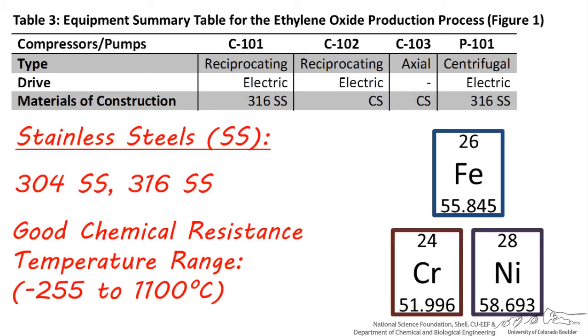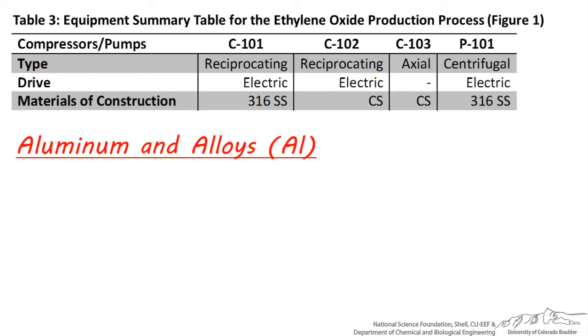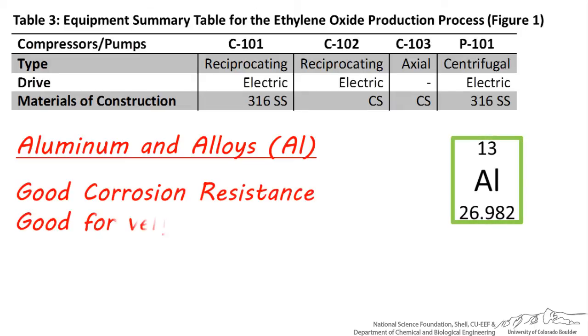Stainless steel is also used for very low and high temperature applications, up to around 1100 degrees centigrade. Aluminum, abbreviated AL, and aluminum alloys are mostly made of aluminum, and are great choices when a light, corrosion-resistant material is required. Aluminum is one of the best choices when very cold refrigerants are being used.